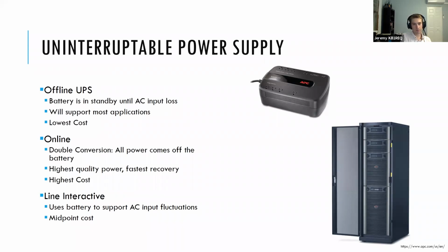A kind of middle point between these, a compromise that takes some of the best of the full online version and makes it a bit more cost effective, is Line Interactive. And that is really always sensing the AC input and has that battery there to condition the voltage coming in and to give you a clean and constant output at all times, no matter what AC is coming into the device. That battery is there to boost it up. So it gives you slightly faster recovery time than offline, but really the main advantage of that is the power quality you're going to get out of it.